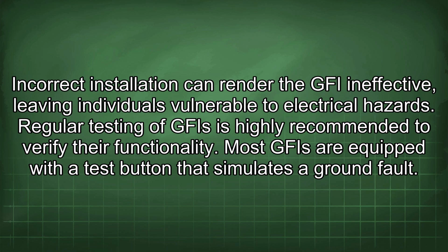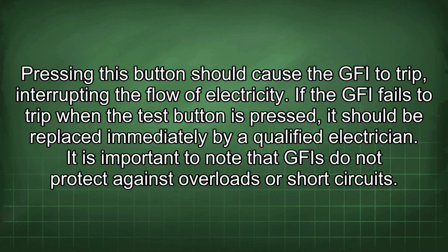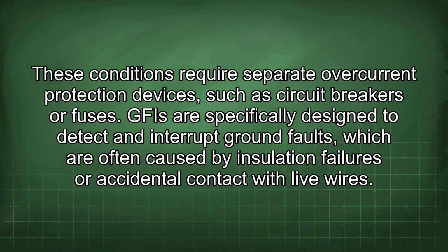Regular testing of GFI is highly recommended to verify their functionality. Most GFI are equipped with a test button that simulates a ground fault. Pressing this button should cause the GFI to trip, interrupting the flow of electricity. If the GFI fails to trip when the test button is pressed, it should be replaced immediately by a qualified electrician. It is important to note that GFI do not protect against overloads or short circuits. These conditions require separate overcurrent protection devices such as circuit breakers or fuses.